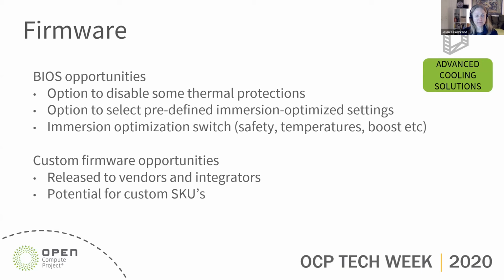an immersion environment. There's also opportunities for custom firmware to be released to vendors and integrators, and potential for custom SKUs here. So some of these considerations, for example, if you're taking a power supply and now you're dealing with maybe the fan has been removed or the fan is not operating, you still need to be able to operate that power supply in immersion, and cooling is being provided by the liquid, right? So those are some of the firmware opportunities there.